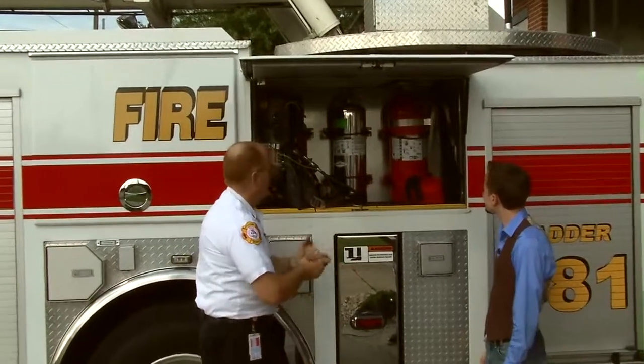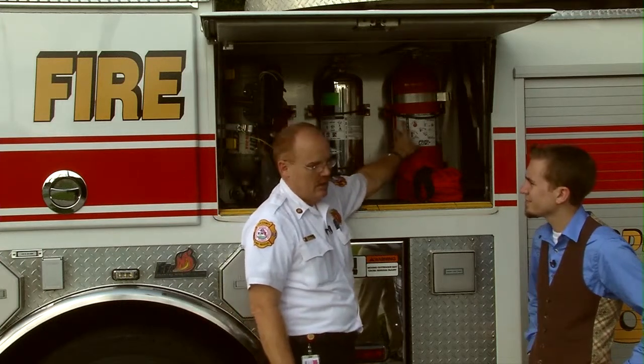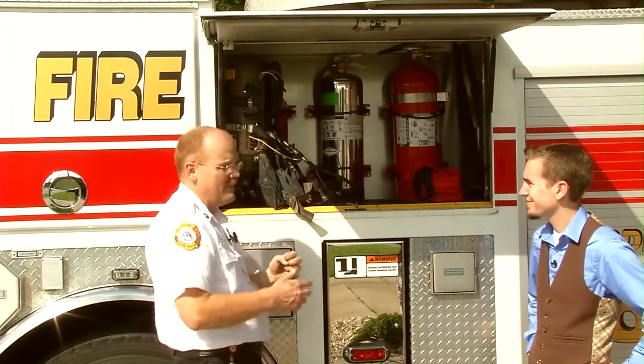In this compartment we have various fire extinguishers. There are small fires that we don't need to pull fire hoses off and squirt water for. There are different forms of fire extinguishers. This one uses carbon dioxide — a compressed gas — and it basically smothers the fire. It occludes the oxygen, so the fire goes out. Remember the basic fire triangle: you've got to have three things to have a fire — heat, fuel, and oxygen — and this one removes that oxygen. The other one is a water extinguisher, commonly called the can. The other one is an ABC dry chemical that uses something like monoammonium phosphate to inhibit the chemical chain reaction of the fire and put it out that way.